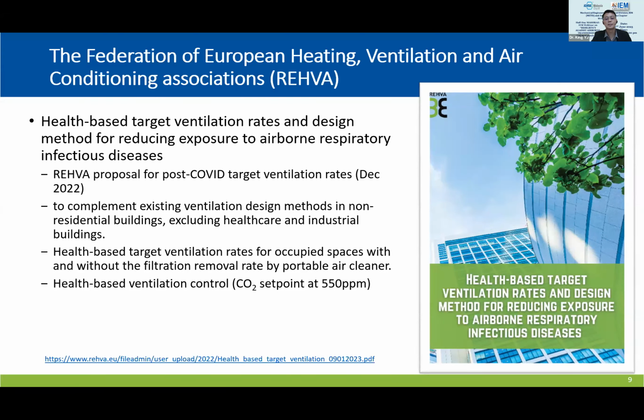This is not a normal ventilation rate. This is the higher ventilation rate used when there is a suspected aerosol infection case. So the ventilation rate is recommended to be increased for occupied spaces, and we can run it with or without the filtration removal rate by portable air cleaners.